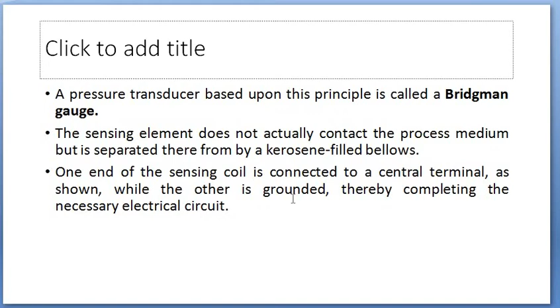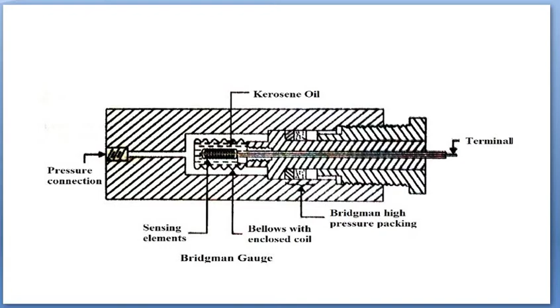The sensing element does not actually have contact with the process medium, but it is separated from the kerosene filled bellows. One end of the sensing coil is connected to the central terminal, while the other end is grounded, completing the electrical circuit. Pressure supply is here, and the sensing element is placed between the bellows filled with kerosene. This high pressure packing is tightly packed and sealed since the pressure is high.